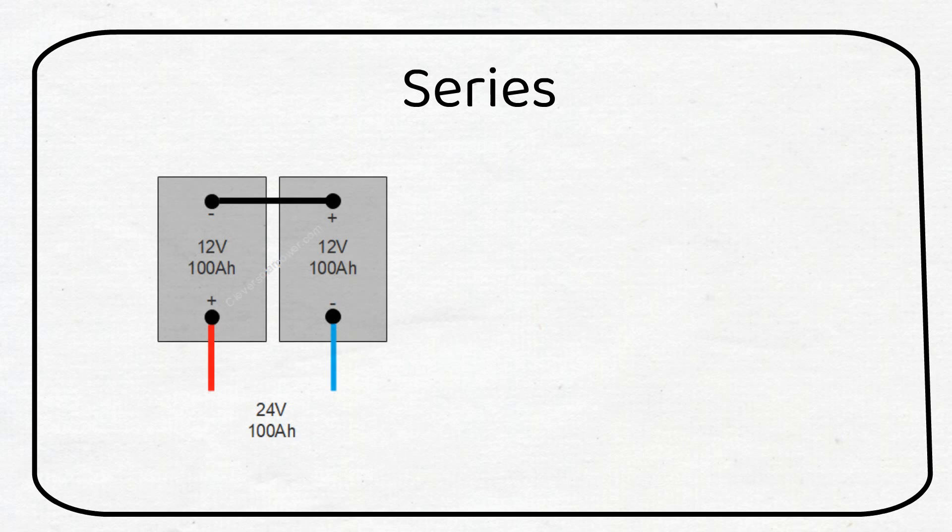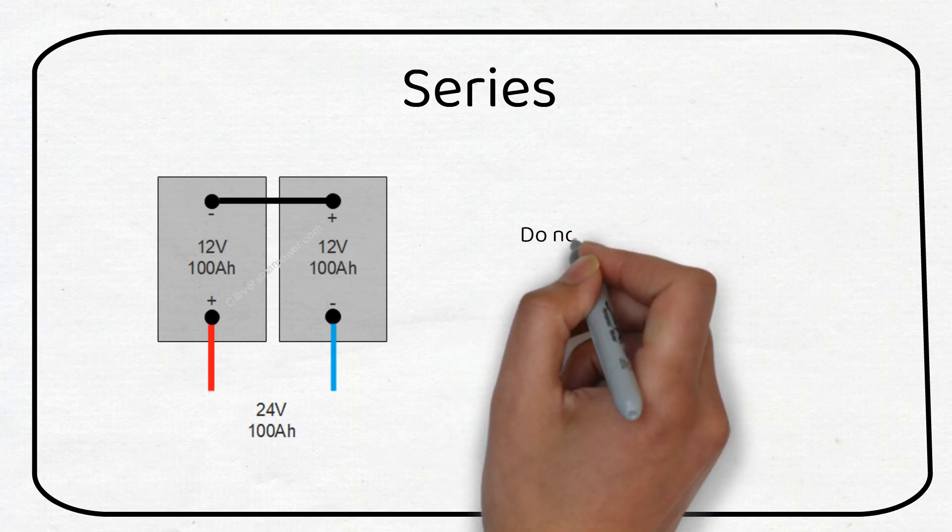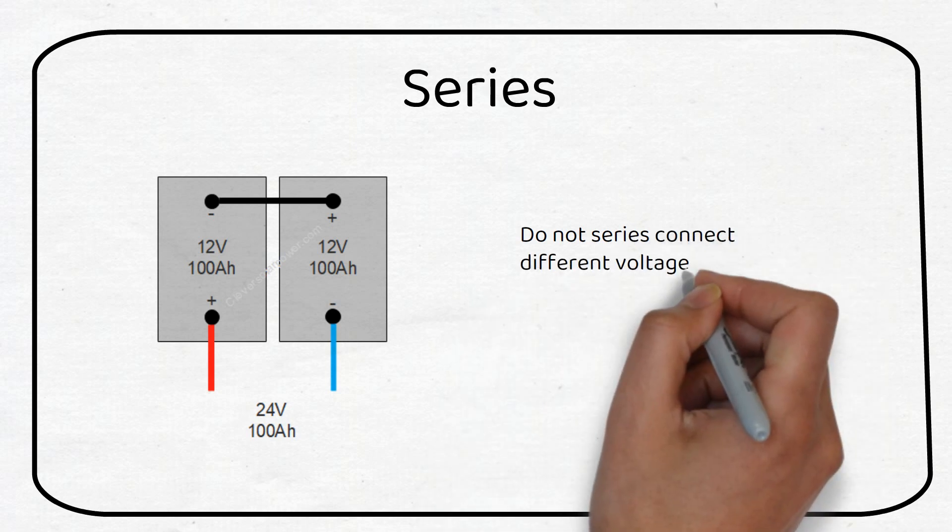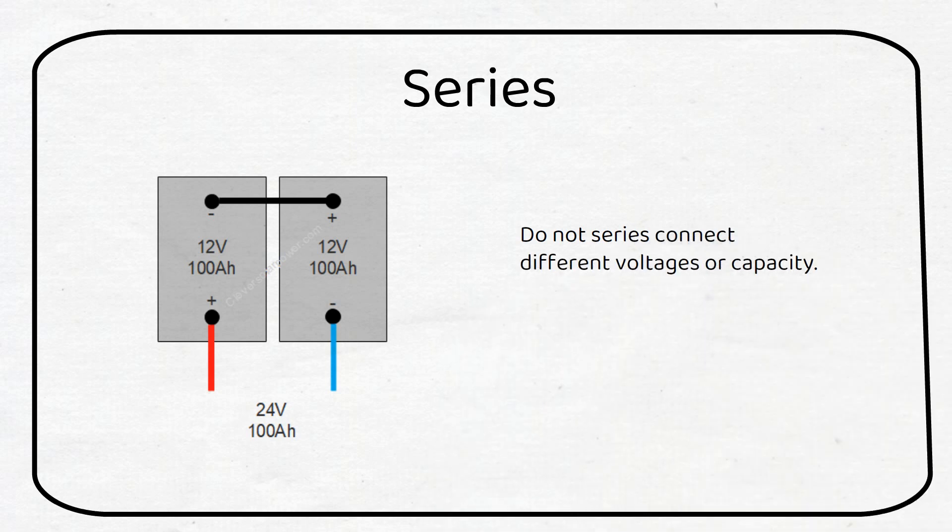If we wire in series the voltage gets added up while the capacity stays the same. Take these 12 volt batteries for example. If we wire them in series we will have a 24 volt 100 amp hour battery. Do not series connect different voltage or capacity batteries.